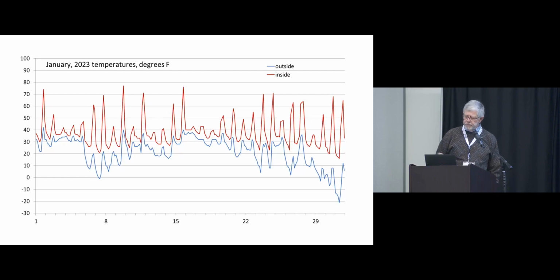The other thing I want to point out is how high those peaks go up during the day. You get up over 70 degrees—that's way more than you need to. So there you've got capacity to put some of that heat away if you've got enough heat exchanger capacity in the greenhouse. That's something that needed to be addressed.